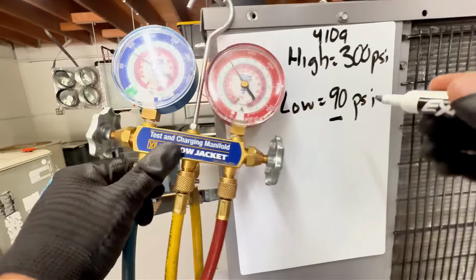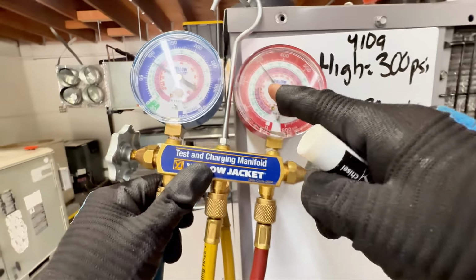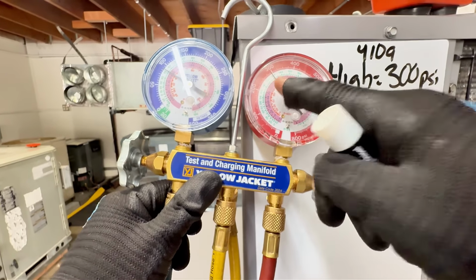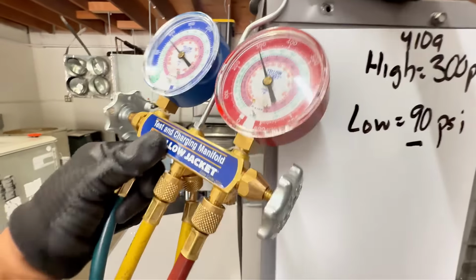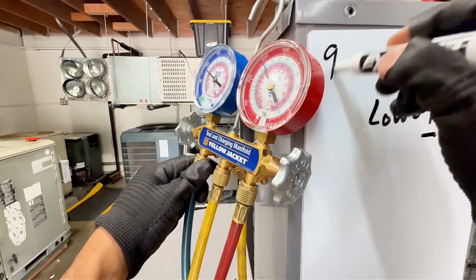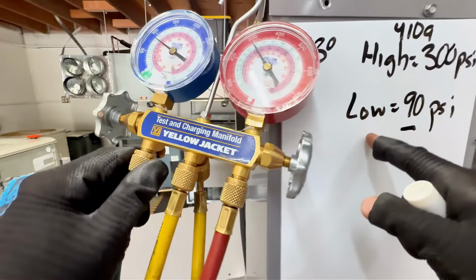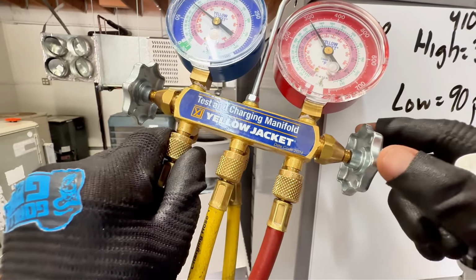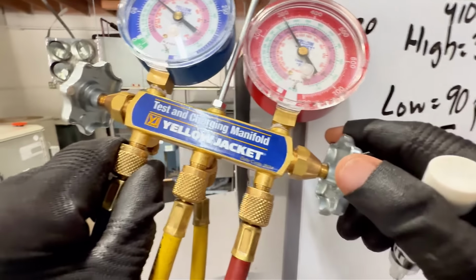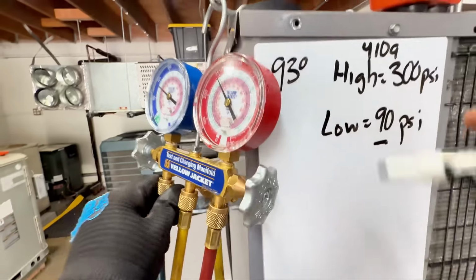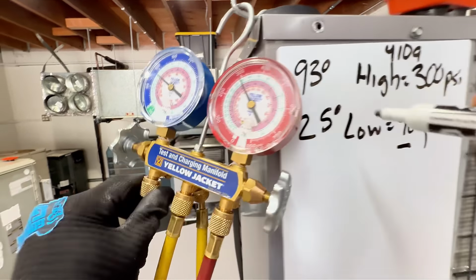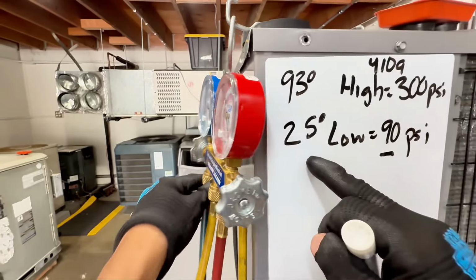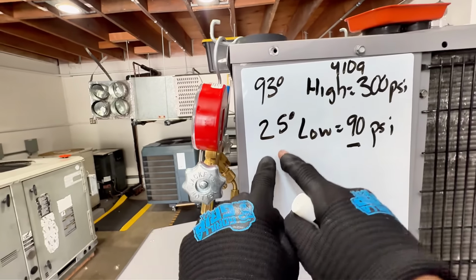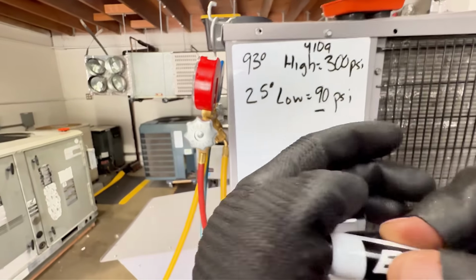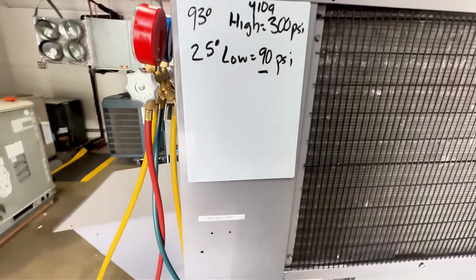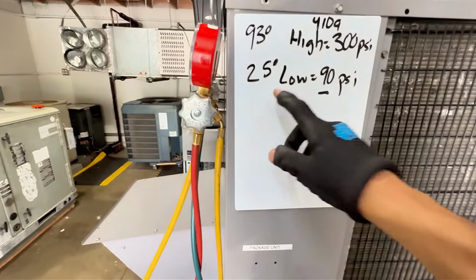Now I'm going to convert them to temperature. So 300 is about 93 degrees. This is 93 degrees, condensing temperature. My evaporator temperature, I'm at 90 PSI, so I'm at, oh whoa, around 25 degrees. That's what I'm looking at over there, 25, 24. Right away, I'm like, oh, it's below 32 degrees. So I might end up with a freezing coil or whatever, right? There's an issue because it's below 32.